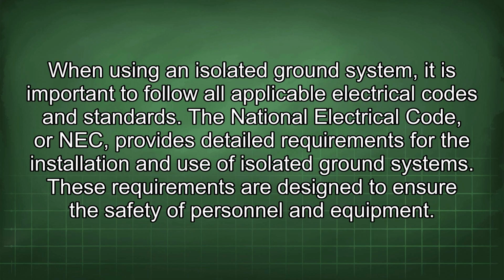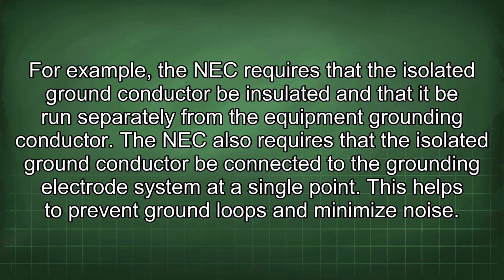When using an isolated ground system, it is important to follow all applicable electrical codes and standards. The National Electrical Code, or NEC, provides detailed requirements for the installation and use of isolated ground systems. These requirements are designed to ensure the safety of personnel and equipment. For example, the NEC requires that the isolated ground conductor be insulated and that it be run separately from the equipment grounding conductor. The NEC also requires that the isolated ground conductor be connected to the grounding electrode system at a single point. This helps to prevent ground loops and minimize noise.